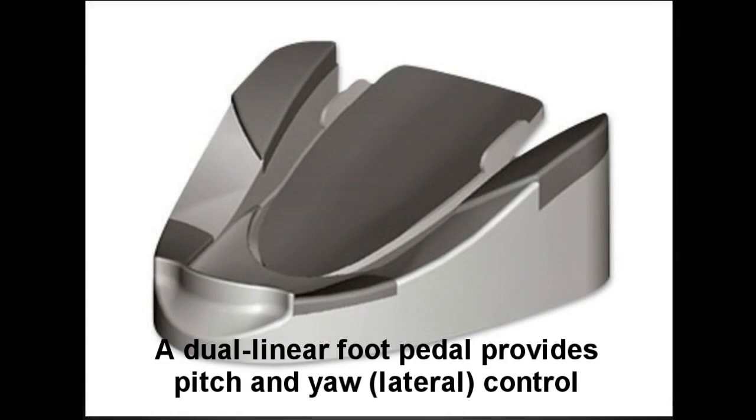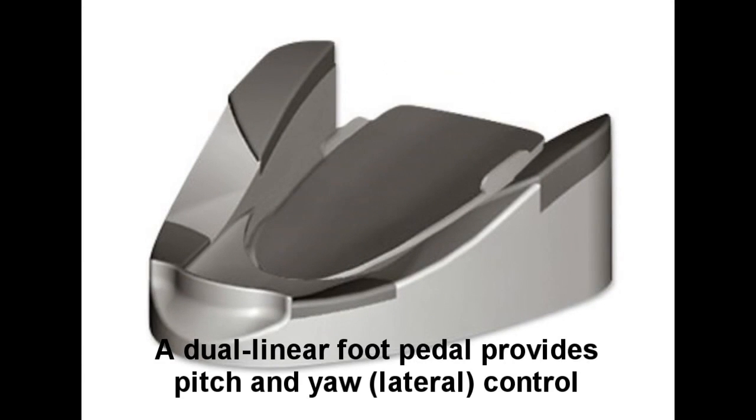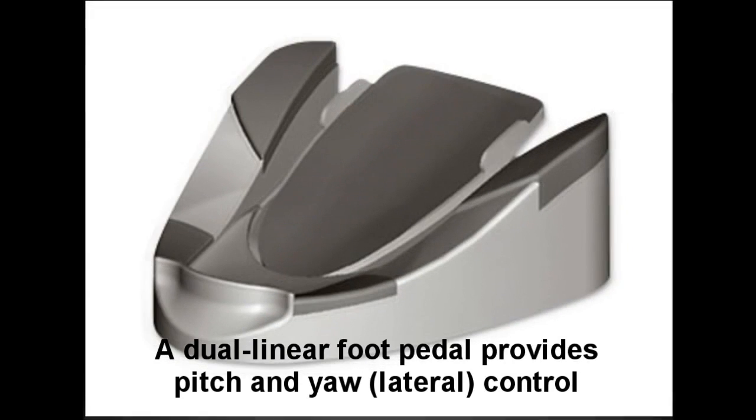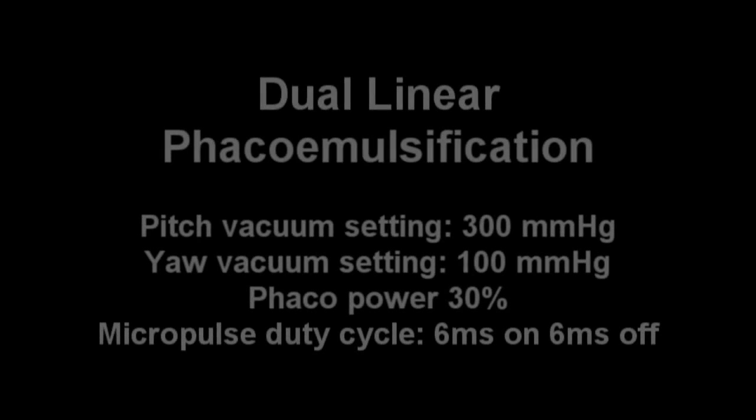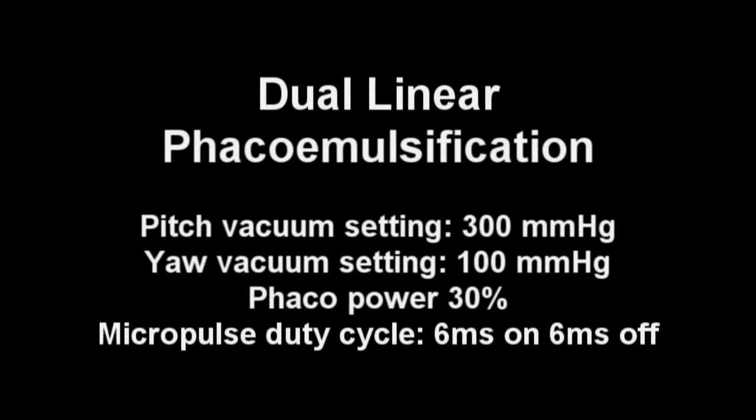It should be noted that the lateral or yaw position can be set for additional phaco power or vacuum, whichever the surgeon prefers. Once I switch over to nucleus removal, my pitch vacuum settings will be at 300, and the yaw setting will give an extra 100.